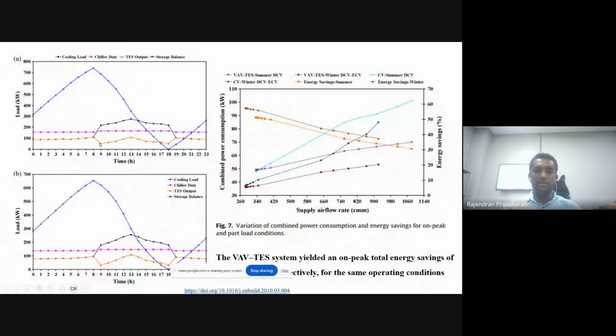because until this point the cold energy was stored, and you can see from 8 AM onwards there is a sudden increase in the peak load. So this peak load is supplemented by the energy stored by the PCM in the TES. With this, you are able to save much more energy as compared to the other systems. This kind of system is available in many places. Even in Chennai, it was available long back. They installed water-based TES in integration with the air conditioners.